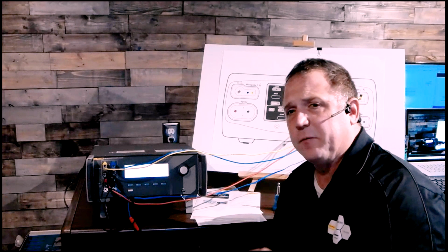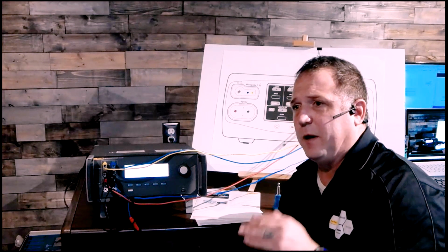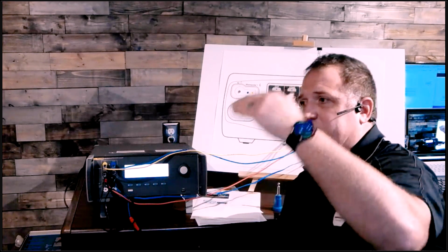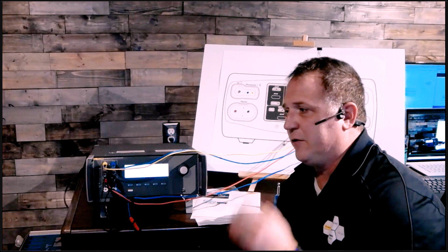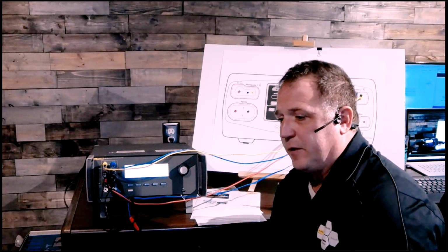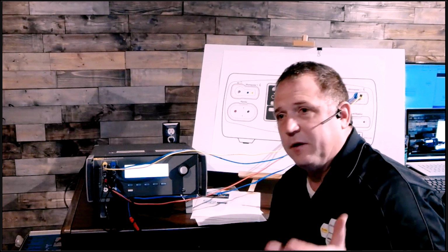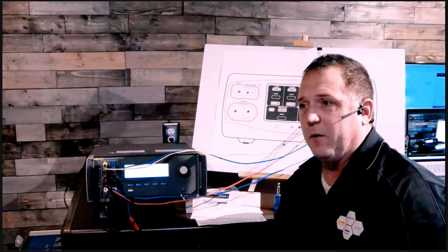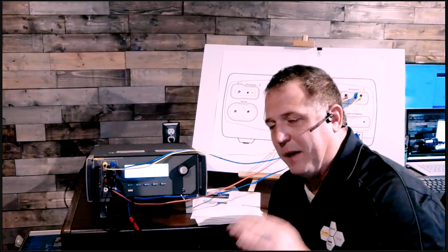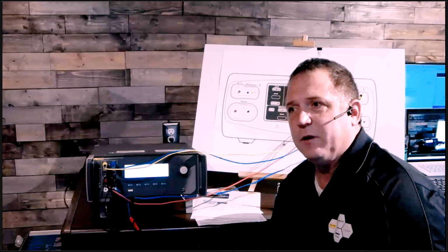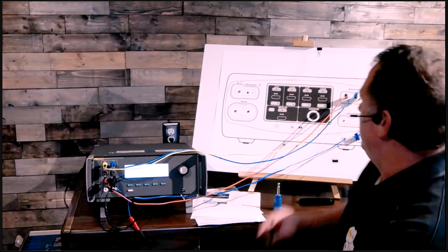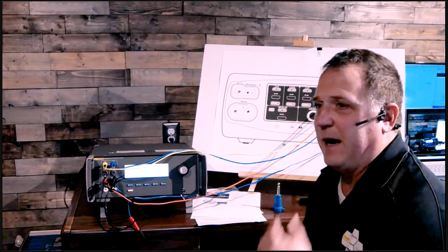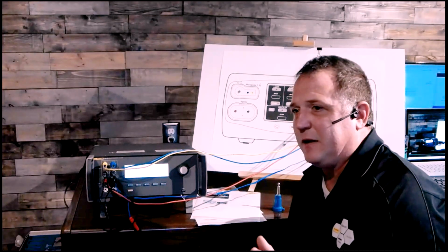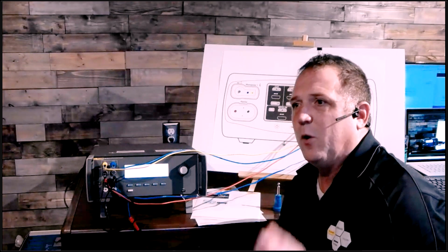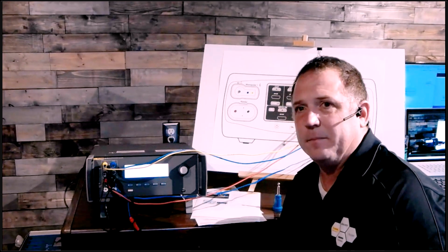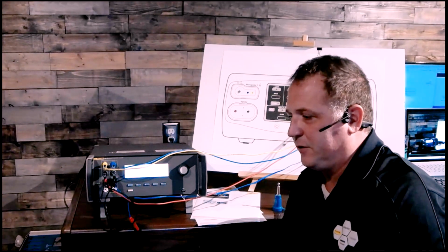If you look in your service manuals, you might find it's going to request that you test multiple points, every so many watts off the scale, rather than just the high end. Some people accept that, but some want to test more and make sure it's working across the full scale.